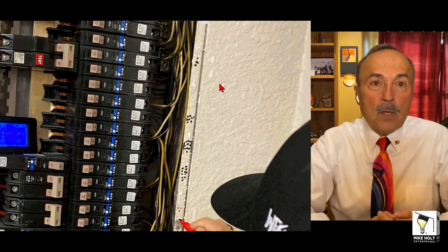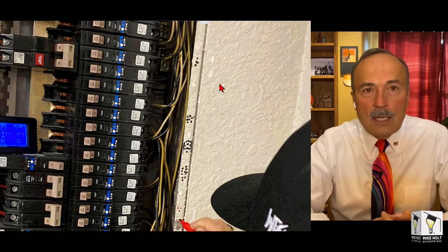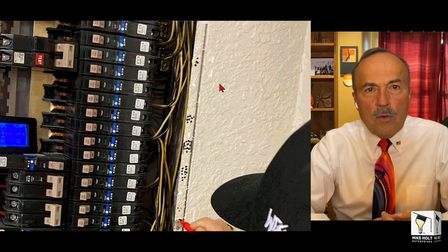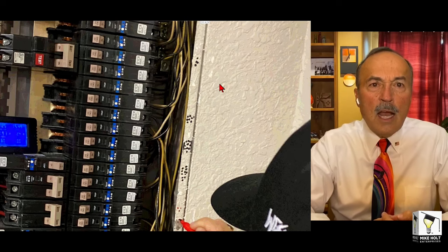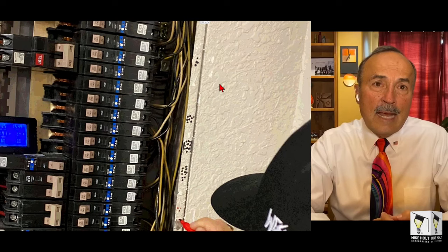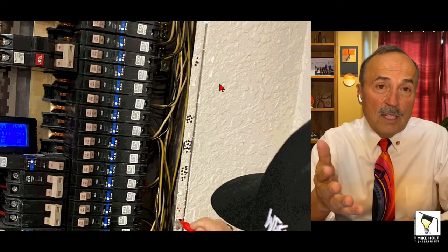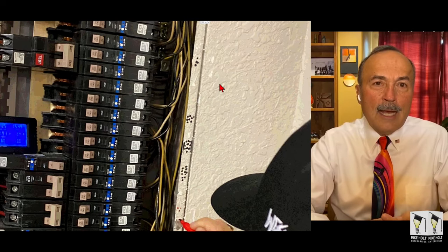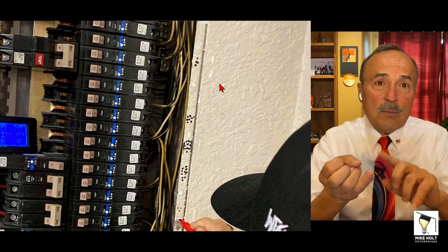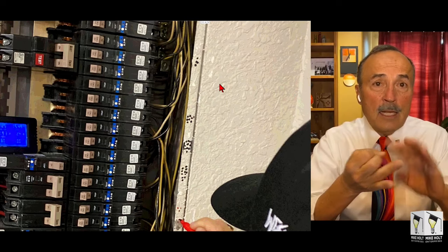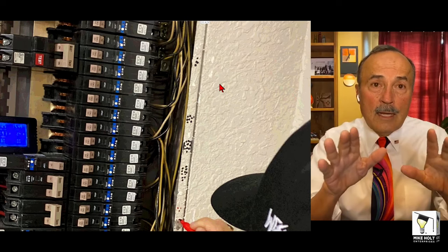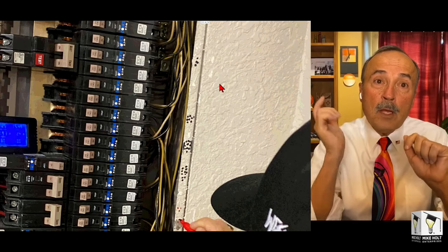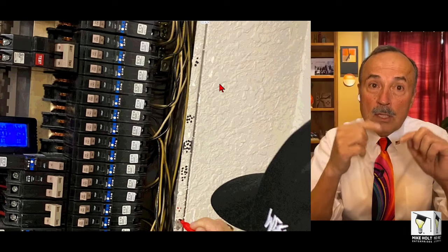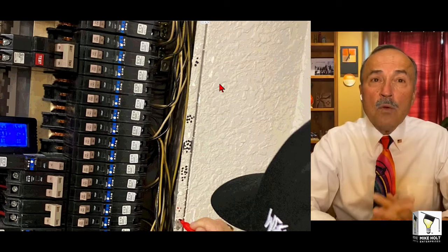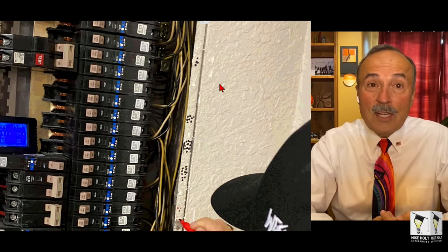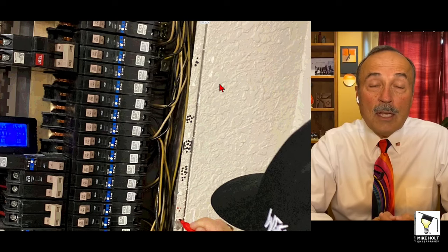Now, my son has done this, and I've heard of guys who say, well, what I do is I go in there, and I take the circuit, and I find out the receptacles were backstabbed, or the switches were backstabbed. These are 15-amp circuits, and I replace that. Listen, you charge the customer money. You didn't fix the problem. So don't do any of that. Just simply pull the breaker out. Take the breaker that was adjacent to it, put it in, get a new breaker on the circuit that was not tripping. And you know what's going to happen? It's not going to be tripping anymore.